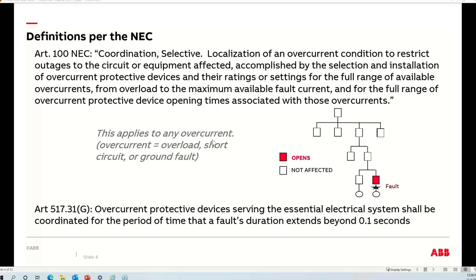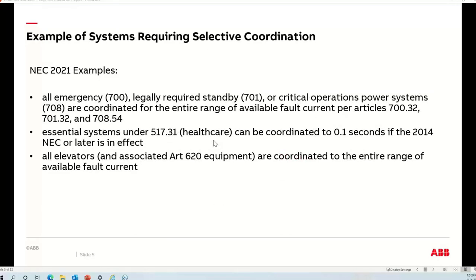Examples of systems requiring selective coordination include Article 700 (emergency systems), Article 701 (legally required standby), Article 708 (critical operations power systems), Article 517 for essential systems in hospitals, and Article 620 for elevators and associated equipment. These are some of the most common ones seen in many designs and facilities.